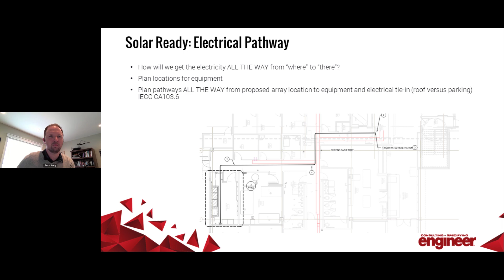For the electrical pathway, you need to consider how you're getting from the rooftop down to the main point of service or the point of interconnection, ideally during the building design, and then make sure your conduit is sized appropriately for the system as well. This is also in the IECC. You don't necessarily need to connect all the way to the gear, but at least have that point A to point B planned, and likely that utility disconnect as well. So you need to understand the utility requirements and where that disconnect needs to go, because that's where you're trying to get back to also.